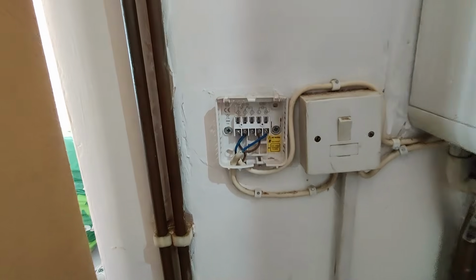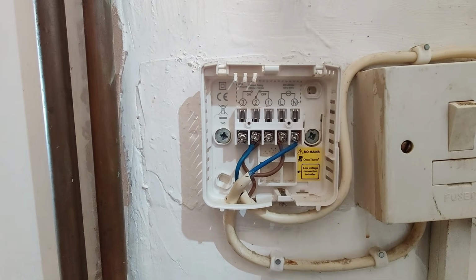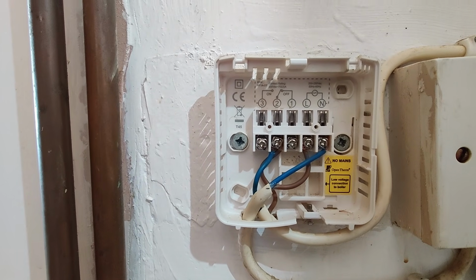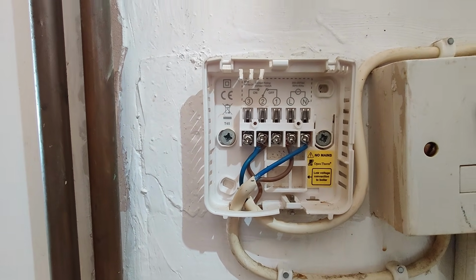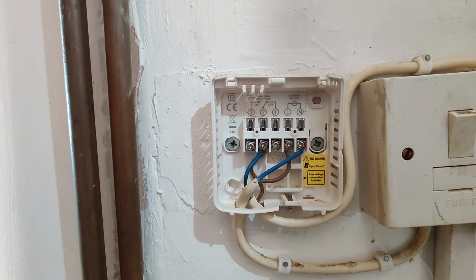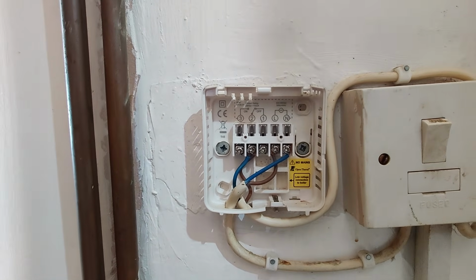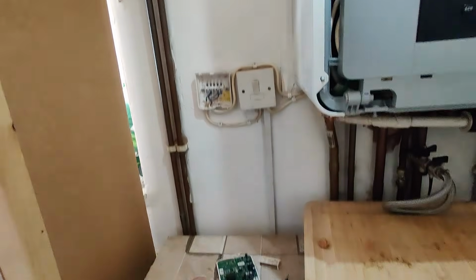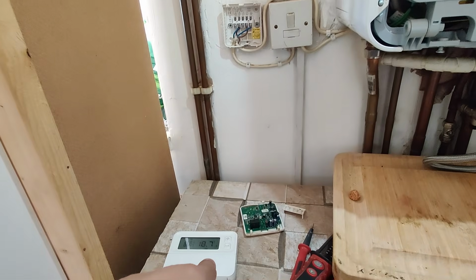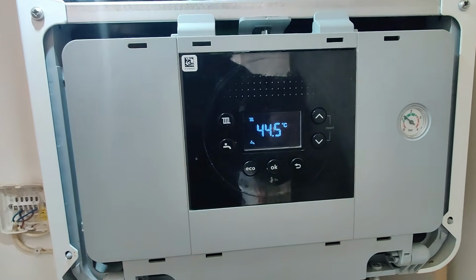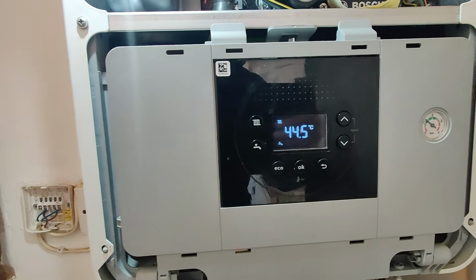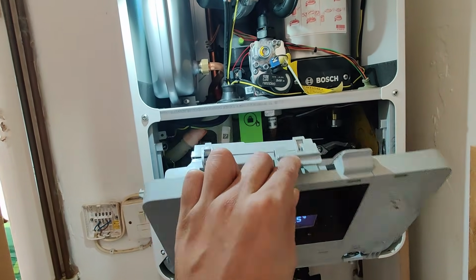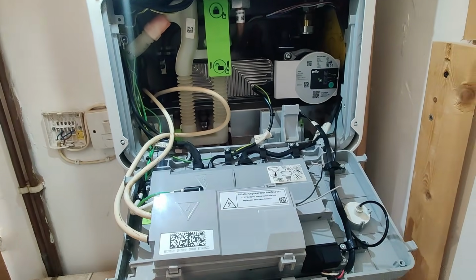So the very first thing I've done, as you can see in here, I've looped the common to normally open. So basically, the loop that we normally remove from the boiler, and then we connect the thermostat. Let's say I created that loop back here. So now the boiler has constant demand. So in a fashion, this programmer is bypassed. But as you can see, there's no demand on the boiler. So the next thing, I opened the cover up for a quick visual, and look what I found.